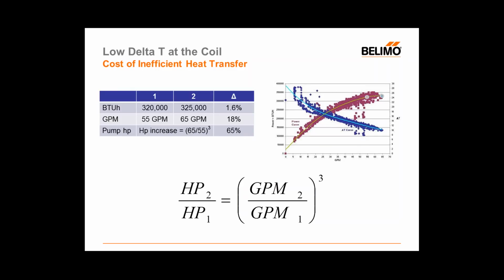Because of that cubic exponent that's in there, small changes in the amount of flow that we're going to have percentage-wise can actually net us a fairly substantial amount of savings. So this would be the big way we could essentially start shifting our pumping costs lower. In this case, 2% more cooling or 1.5% more cooling is costing us 65% more dollars. If we had the ability or the knowledge to know that and make a decision about it, I don't think anybody would agree that that's a good investment.